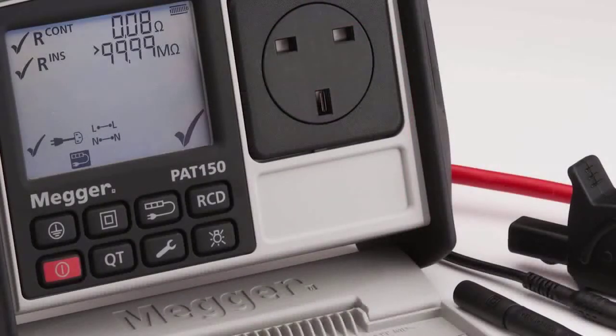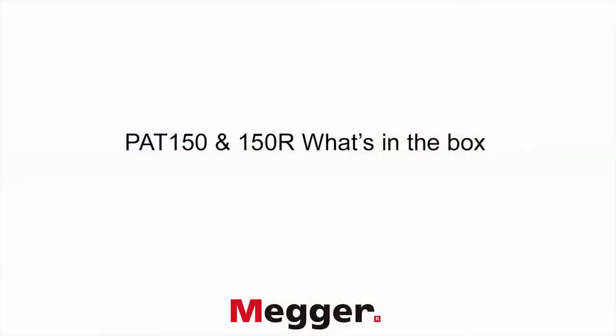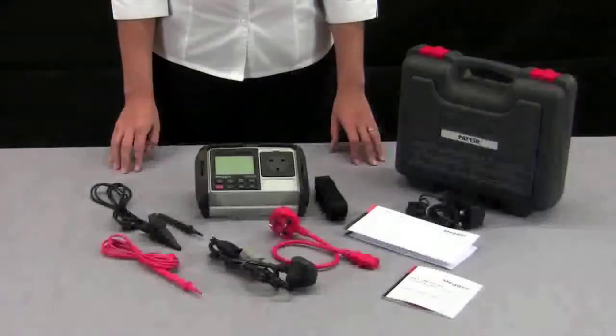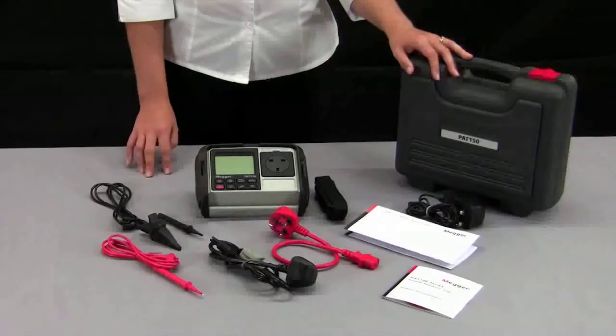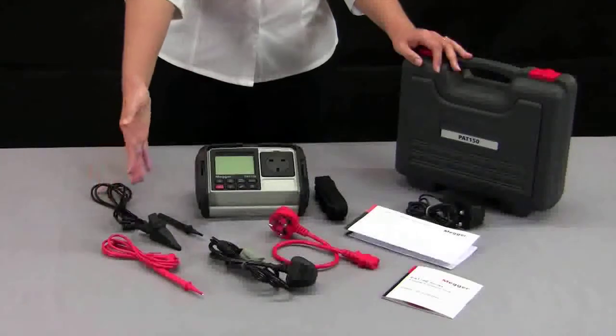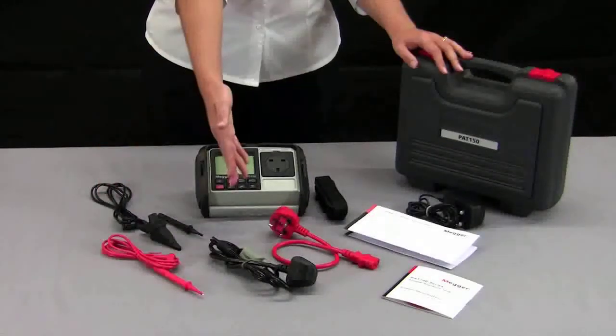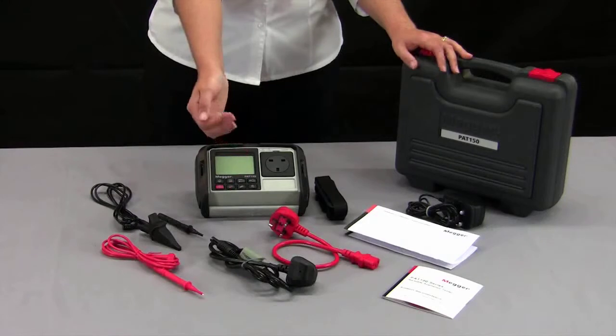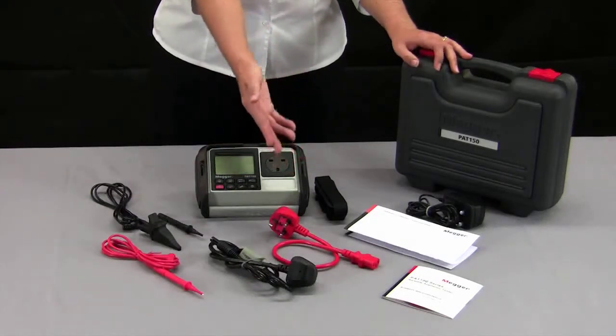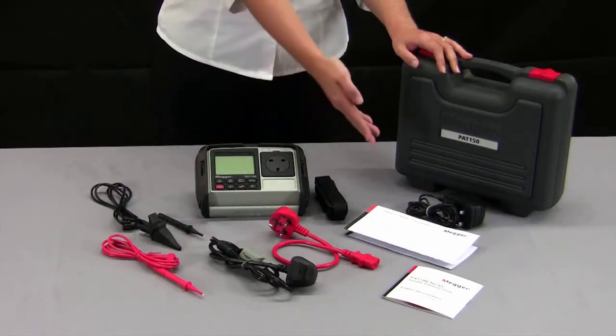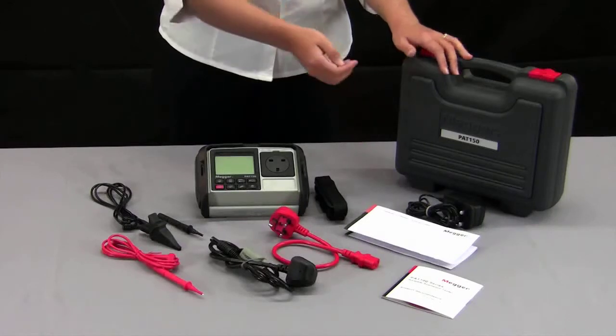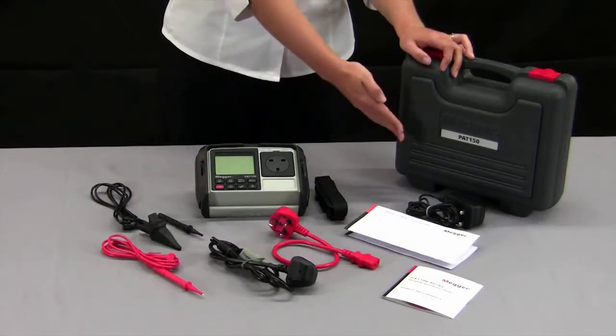And now we'll run through the PAT150 and the 150R. Supplied in the box with the PAT150, you have your earth bond lead, the potential probe, the mains lead for live load leakage testing, your extension lead adapter, your neck strap, a calibration certificate, and for the PAT150R you also have your charging lead.